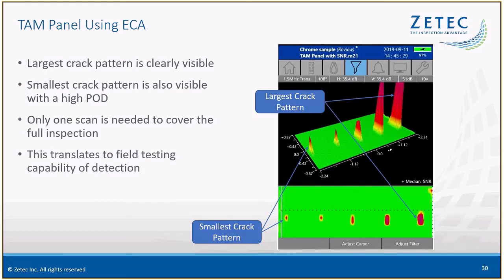Also, if you look at that plate, it took less than a minute to set up and perform this exam. And the actual inspection, once you're set up, takes just seconds. You can scan it, and in seconds you have this data. And then you can save this data file if you want to have a historical record or see if things change over time.